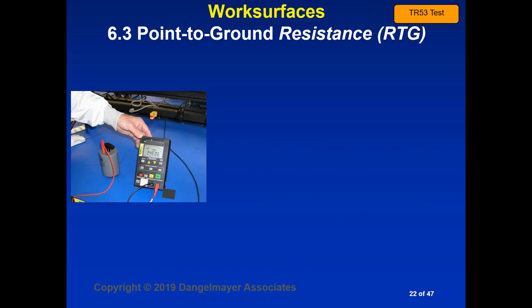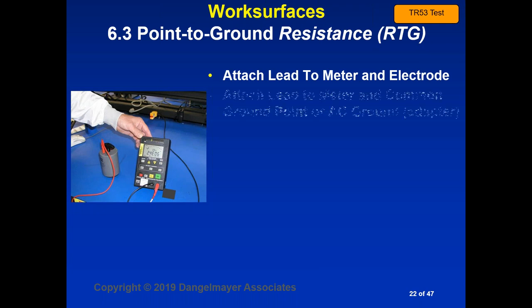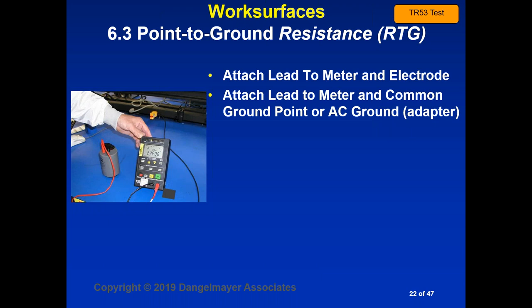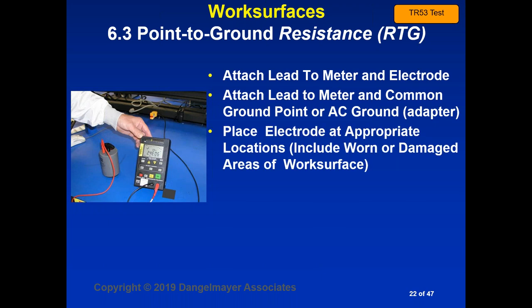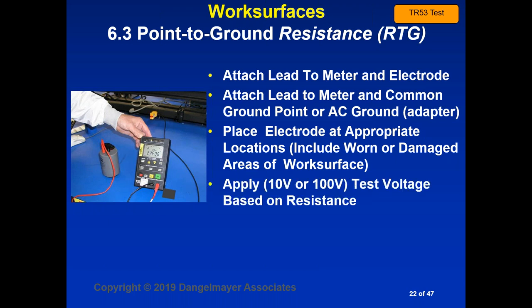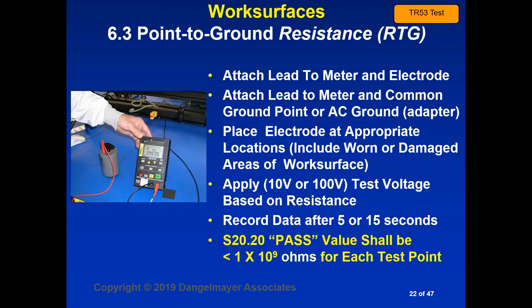So here's our measurement procedure. First of all, attach a lead to the meter and the electrode. Attach a lead to the meter and the common point ground or the AC ground adapter. Place the electrode at appropriate locations on the work surface. You try to include worn or damaged areas if you can see them on the work surface. Then you apply 10 or 100 volts depending on resistance. And then record the measurement after 5 or 15 seconds. You can see here this particular work surface measured 2.4 times 10 to the 6th ohms, which is less than the S20.20 pass value of 1 times 10 to the 9th for each test point.